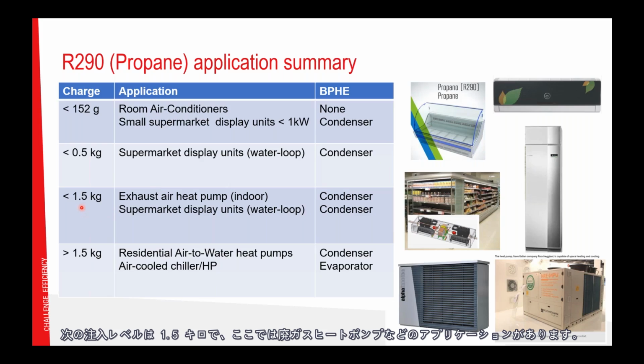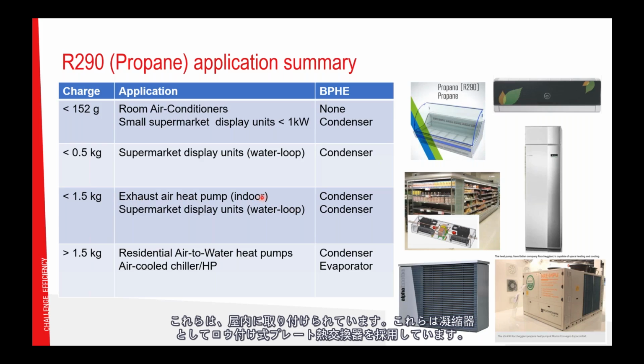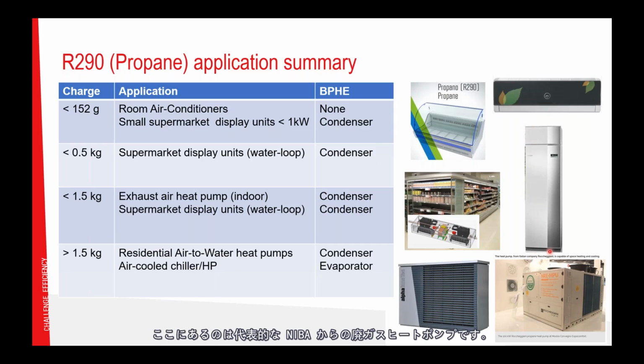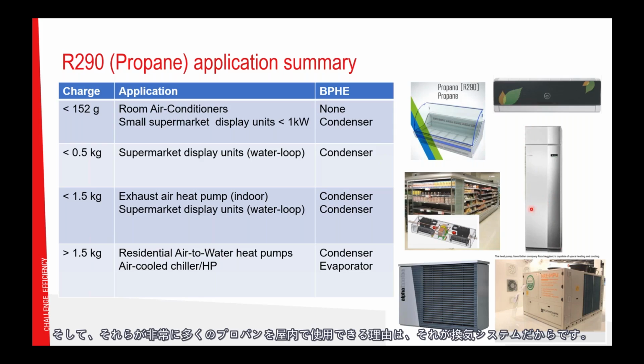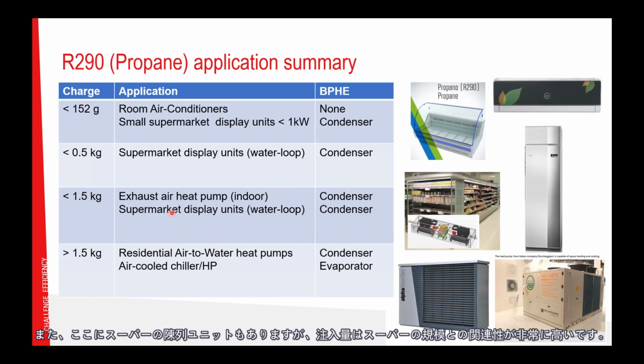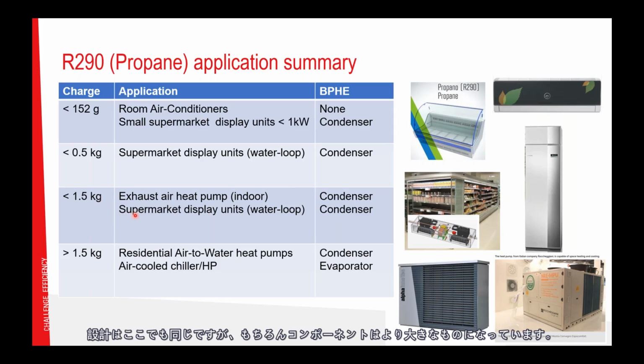The next charge level is 1.5 kilos. And here we see applications such as exhaust air heat pumps. They are mounted indoors, and they use a brazed plate as condenser. You can see here a typical exhaust air heat pump from NIBE. And the reason why they can use so much propane indoors is that it is a ventilated system. Heat is being extracted from the indoor air and then rejected outdoors. So it's continuously being ventilated, and for that reason, propane can be used. Also here, we have supermarket display units, and the charge is very much related to the size of the supermarket. Here it's the same design, but of course with larger components.